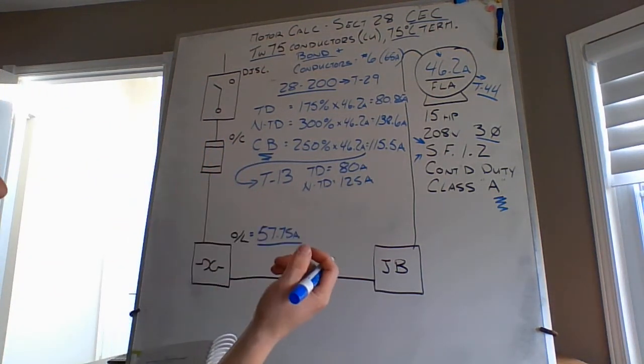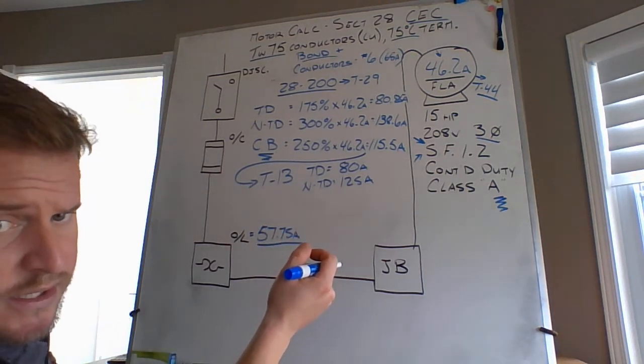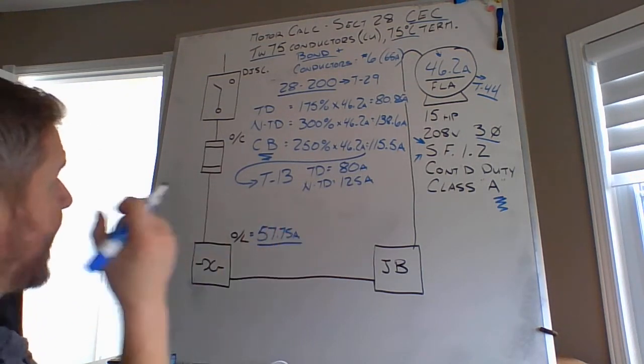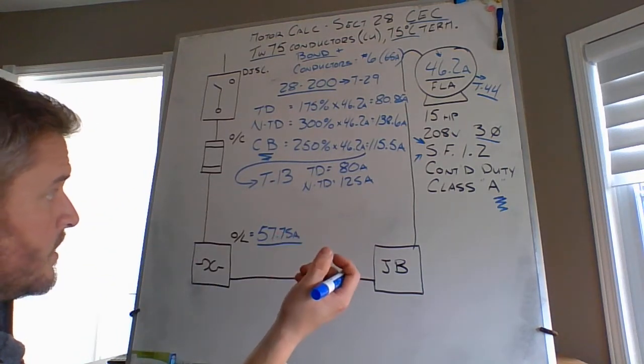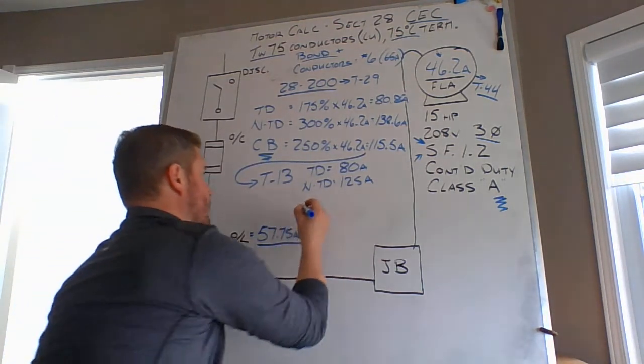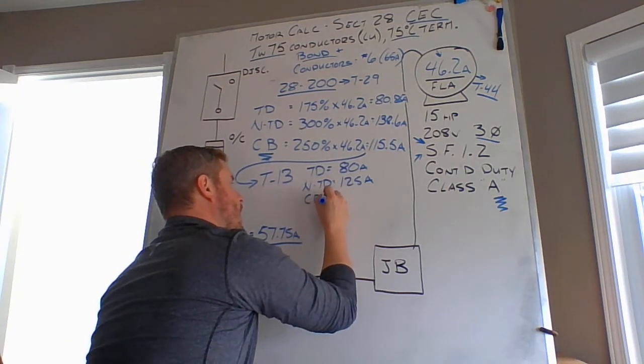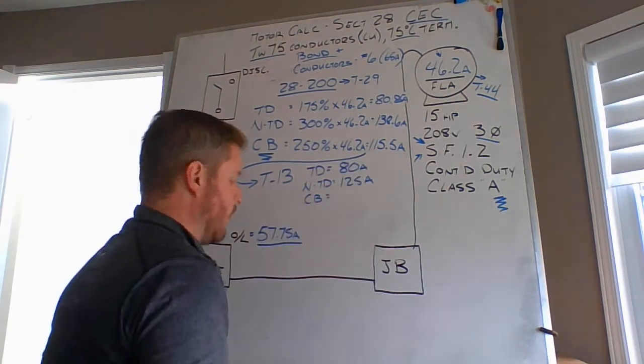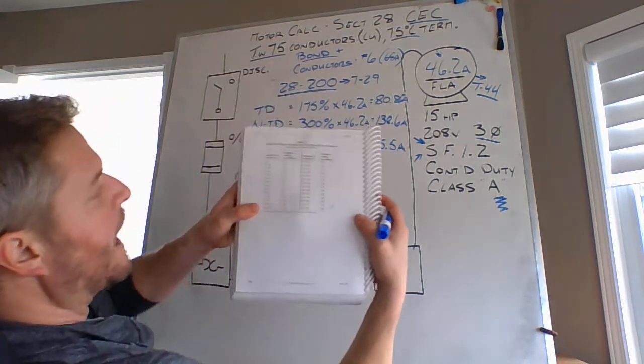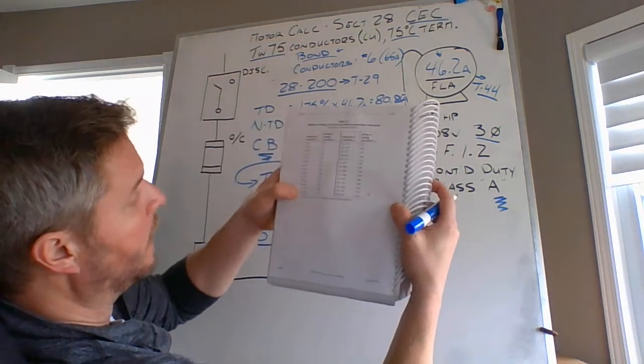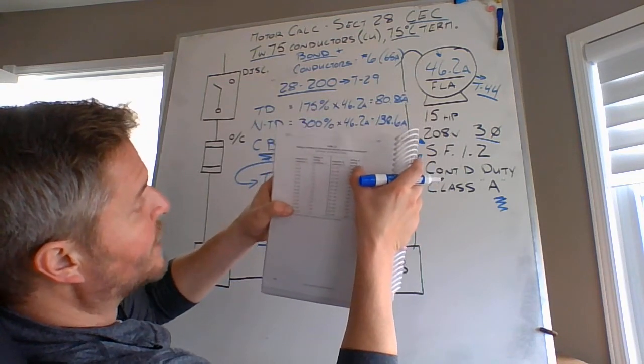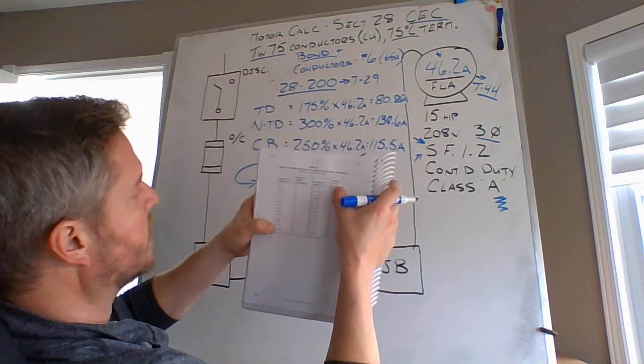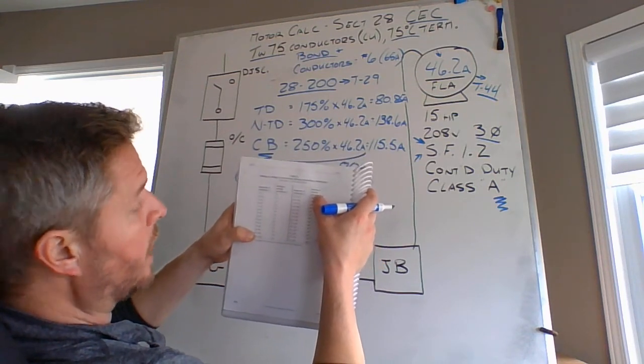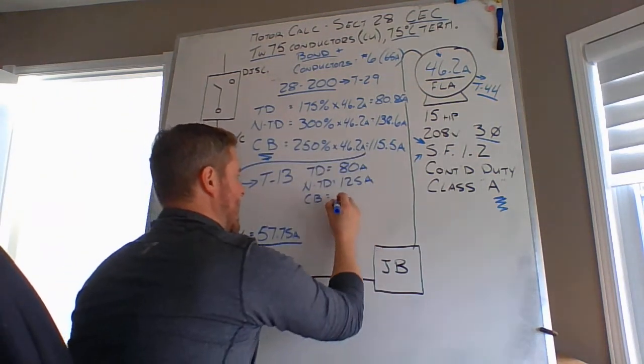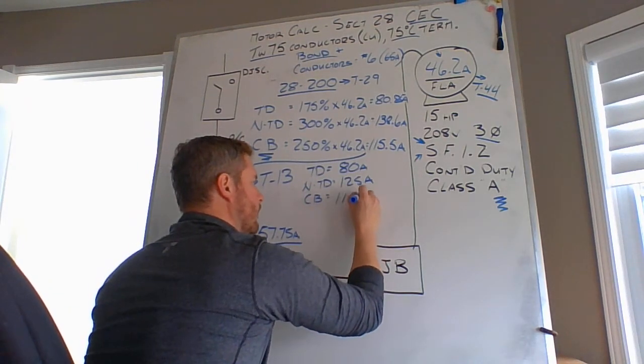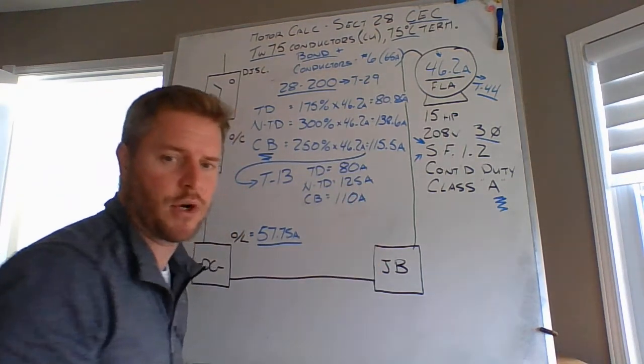And then once again for the circuit breaker at 250%, my FLA, I calculate 115.5 amps. So for a circuit breaker, I cannot exceed that 115.5. In that case, I go back right to my table 13 right here, and I see I cannot put in the 125 because that far exceeds my 115.5 amp calculated maximum. I have to install a 110, a 110 amp circuit breaker.